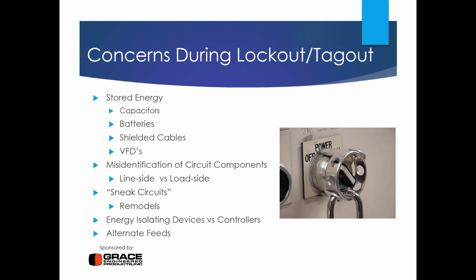And we've already covered alternate feeds under the sneak circuits, but do suffice it to say that transfer switches and alternate generating sources are sources of potential alternate feeds. For those of you that do work on high voltage systems, station power transformers and potential transformers used for metering and relaying also represent alternate feeds that need to be isolated.